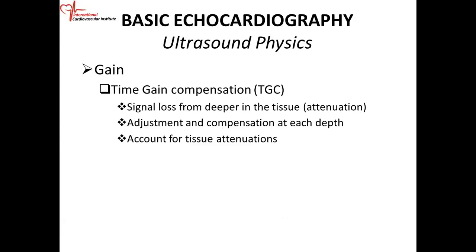So you have to know what TGC stands for and how to use it. So TGC means time gain compensation, and all you're doing is increasing the gain to just that segment that you need. And when you're scanning today, look at the machine, and you will see that there is a series of buttons that you can increase the gain to just that segment that you want. Okay?